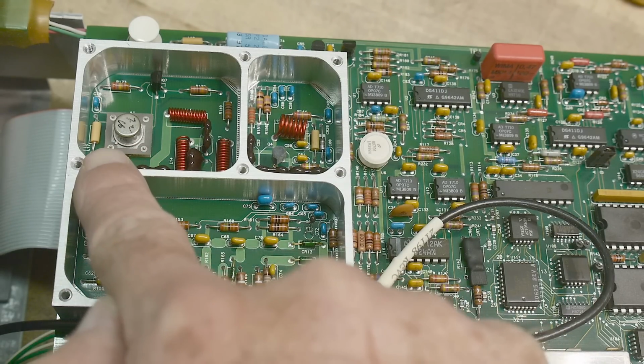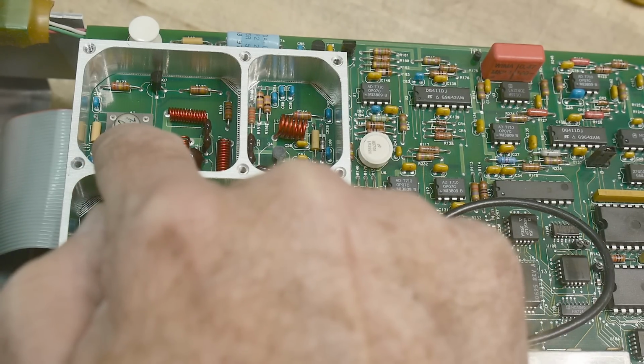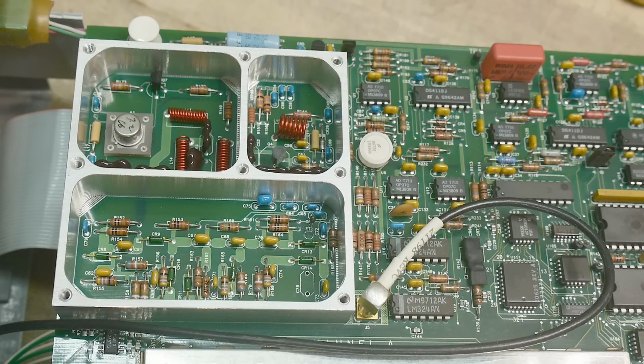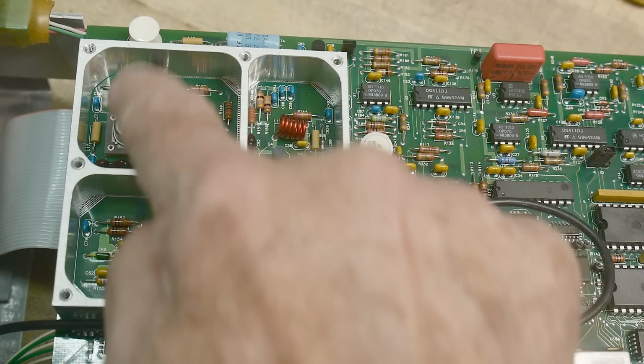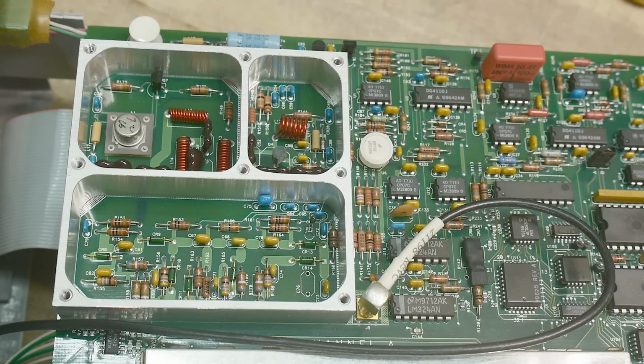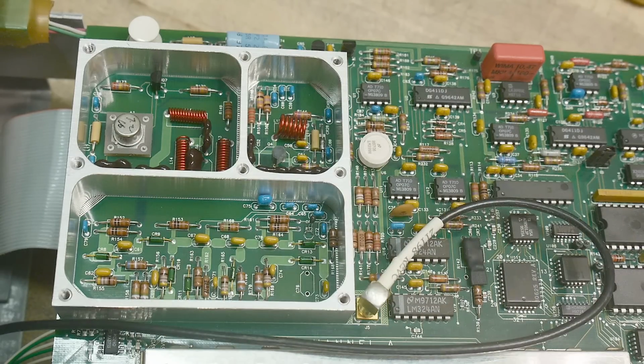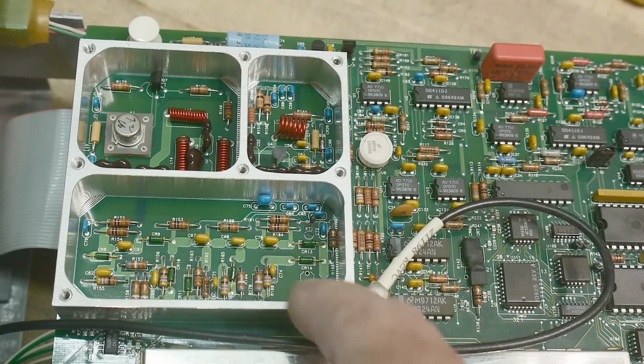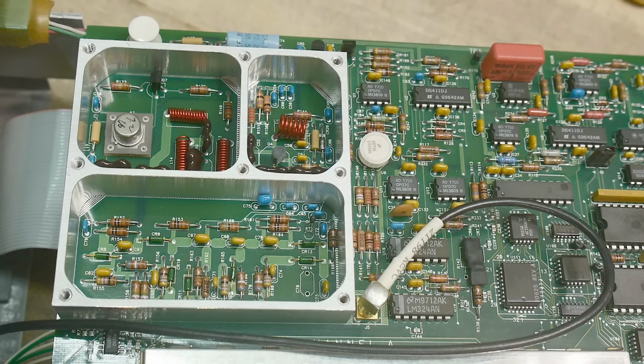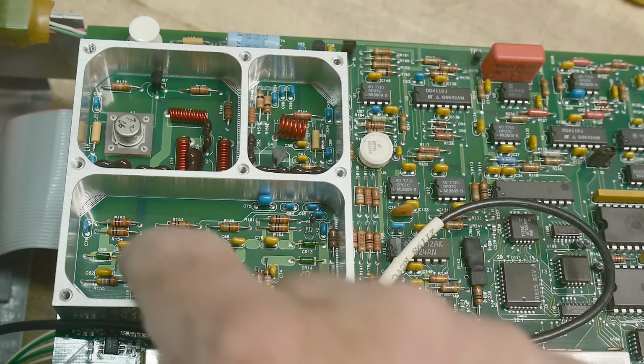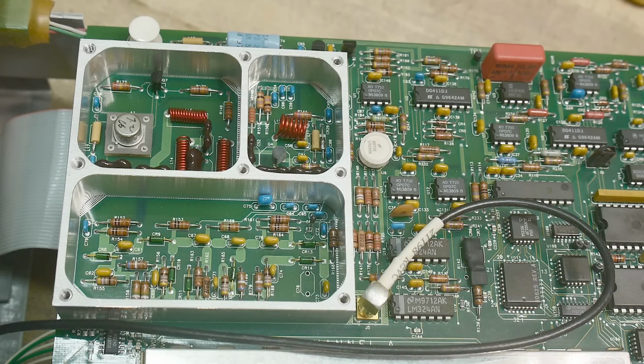Okay, so this is the power meter inside the power meter. You can see that funny little can there on a PC board. It's a Teflon PC board. And that is a thermistor-based power meter. And so that's what this is. So this is a thermistor-based power meter that gives you at least 1 decade of dynamic range, okay? Now, down here is the step attenuator. So this is the step attenuator that allows you to then transfer it up to or down to other ranges of the meter. So this is all PIN diode switching step attenuator stuff.